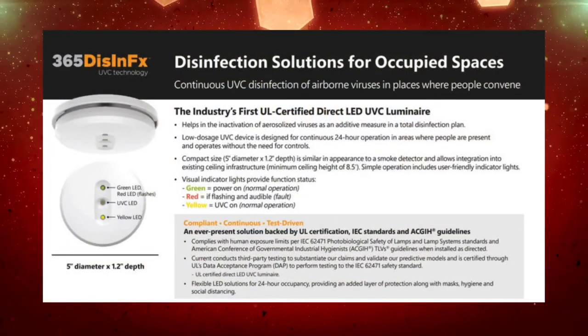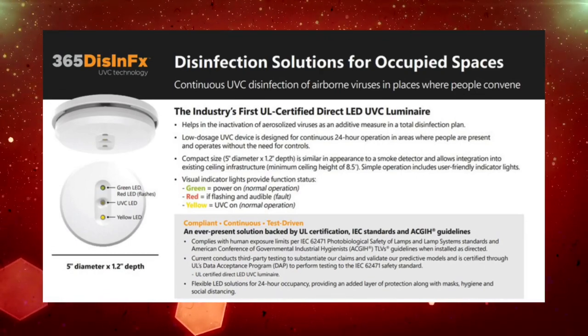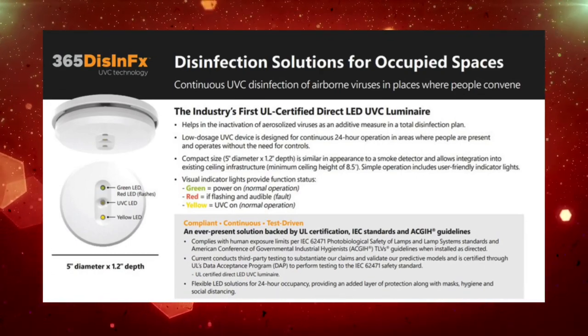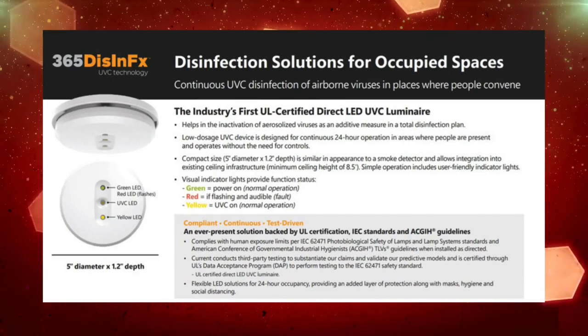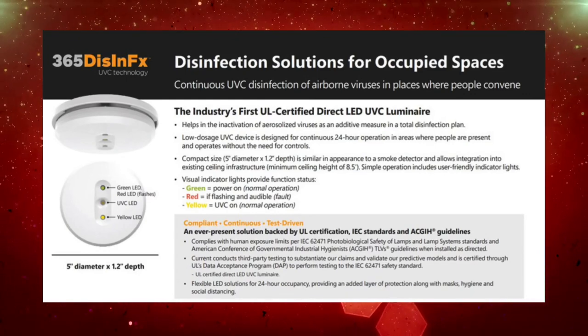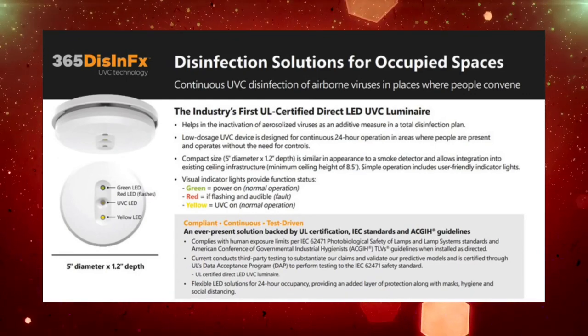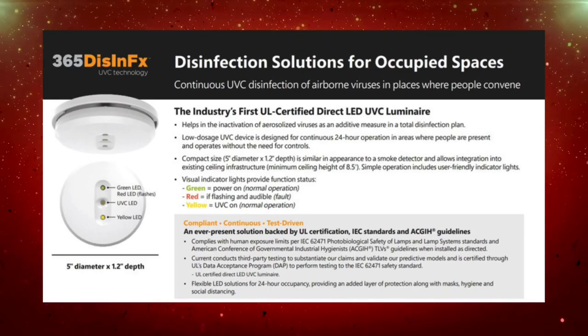Most importantly, I want to note that the LPU 365 Disinfect Puck is the first UL certified direct LED UVC luminaire for occupied spaces and complies with human exposure limits per the IEC 62471, as well as being backed by the ACGIH guidelines.